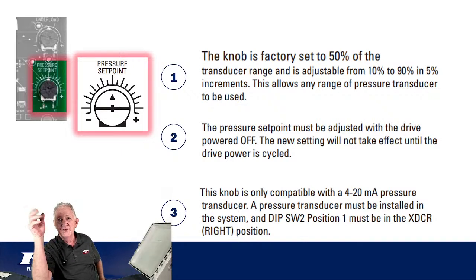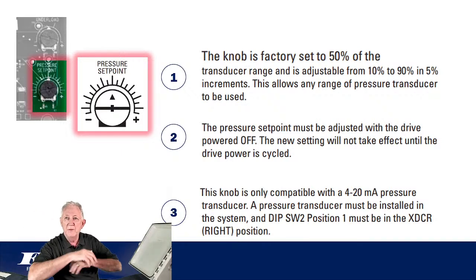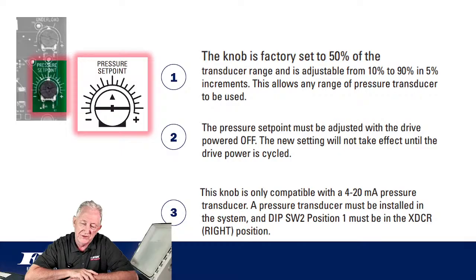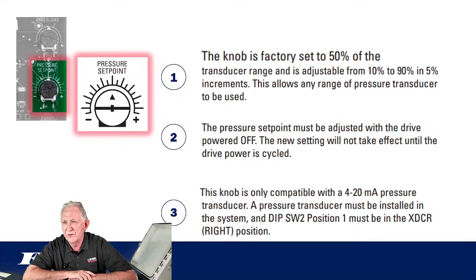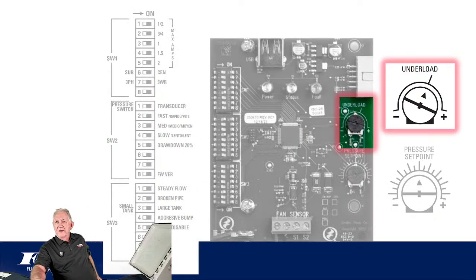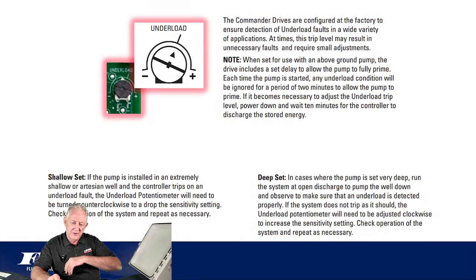All right. So again, this knob is compatible with a 4 to 20 milliamp pressure transducer, which is pretty standard in the industry. The pressure transducer must be installed in the system, and dip switch SW2, position 1 must be in the right position, that XDR, I'm not sure about that one. That's dip switch 2 on that 2-wire drive. I think we're getting down to the last one, the underload, and I'm just going to read another couple paragraphs here because it's easier.